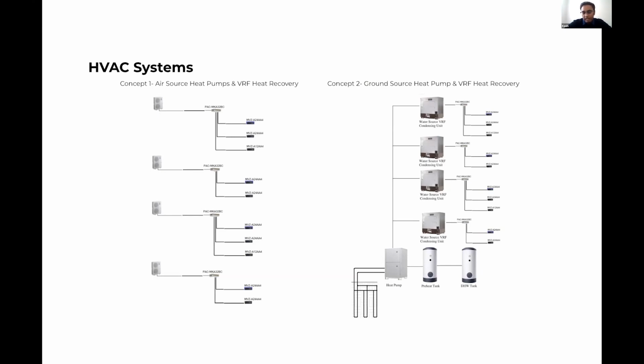In our second concept, the idea is to have a ground source heat pump connected to a water source VRF condensing unit, domestic hot water tank, and a preheat tank. Downstream of the condensing unit will be a similar VRF configuration as our first concept, but this system will have better heat recovery and energy performance.